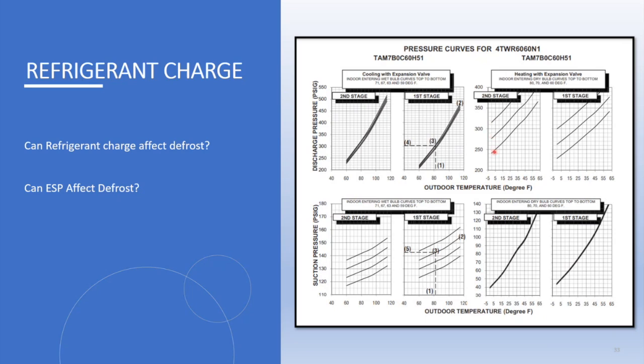This is your high side pressure, and this line would be if it was 60 Fahrenheit in the house. This is 70 Fahrenheit in the house, 80 Fahrenheit in the house. So if it was, say, 35 Fahrenheit outside, 70 Fahrenheit in the house, you would be looking at about 345 PSI head pressure.